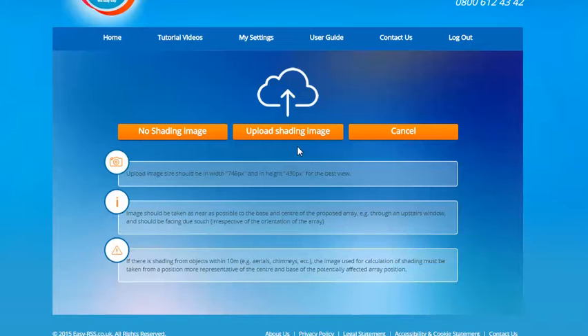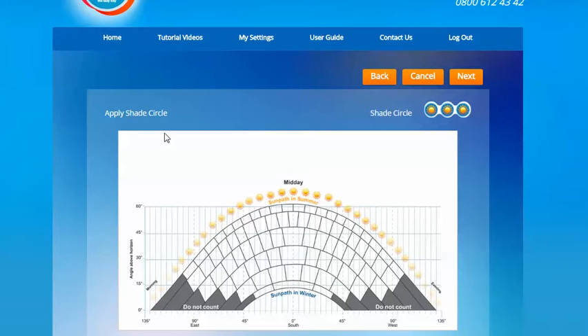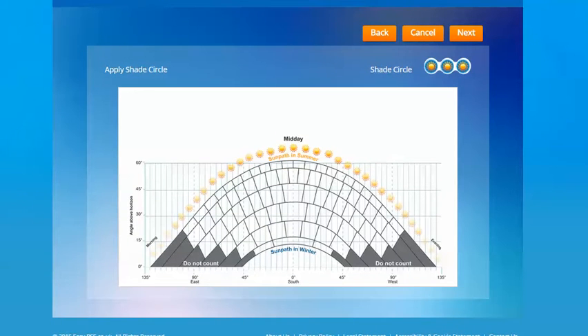Either through an upstairs window or preferably on the roof as close to the array as possible and should be facing due south regardless of the orientation of the panels. The horizon line should also run along the bottom of the image so that the sun path diagram sits at the right position. If you don't have an image to upload you can select the no shading image option and this will take you through to the sun path diagram with the white plain background sat behind it.